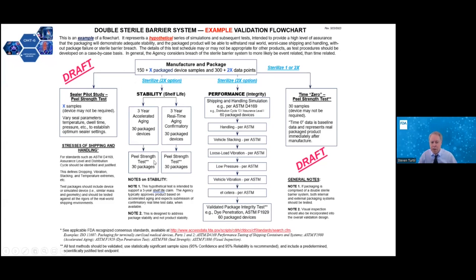And then that's followed by peel strength testing. We do accept this as temporary evidence, but at the same time, you should be starting real-time aging. This is confirmatory testing, and it should also be followed by the same test type, peel strength, typically performed. Again, there are other possibilities when it comes to the test type, but the peel strength is what we see the most of.